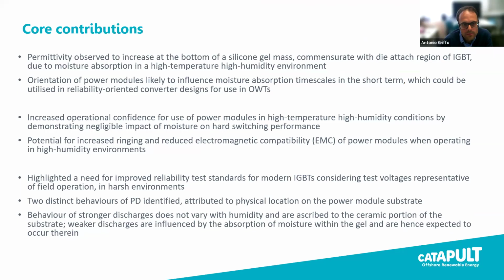Next, please. So this brings us to the conclusion. We have undertaken a number of investigations related to the reliability and influence of humidity on silicon gel performance as used in standard IGBT power modules. We have observed a significant increase in permittivity, which ultimately results in a significant increase in equivalent capacitance of the silicon gel, which again is due to the ingress and penetration of humidity. The orientation of power modules is likely to influence moisture absorption. Again, this can be an interesting outcome of this research and can influence the layout and construction of power converters in applications where this could be a concern.